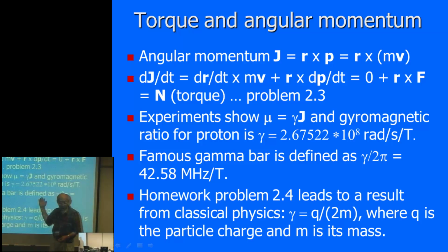And so now, of course, if you have been using this number for a while, for any calculation, then you will remember it pretty well, even down to the total of 4 digits. If you don't remember, you say, well, roughly what's gamma bar? Roughly it's actually 42 megahertz, 42, 43 megahertz. So when you hear people say at 1.5 Tesla, what is the frequency of that magnet at 1.5 Tesla? Well, typically people may say 63 megahertz or 64 megahertz.